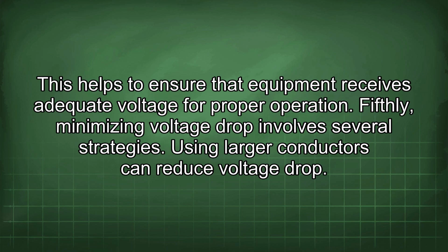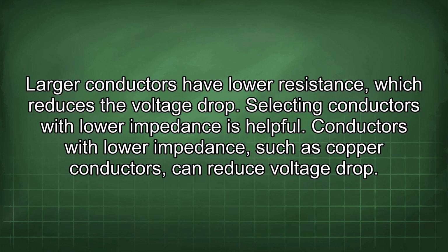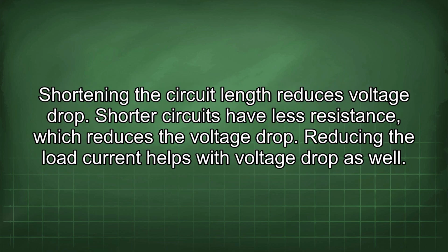Fifthly, minimizing voltage drop involves several strategies. Using larger conductors can reduce voltage drop. Larger conductors have lower resistance, which reduces the voltage drop. Selecting conductors with lower impedance is helpful. Conductors with lower impedance, such as copper conductors, can reduce voltage drop. Shortening the circuit length reduces voltage drop. Shorter circuits have less resistance, which reduces the voltage drop.